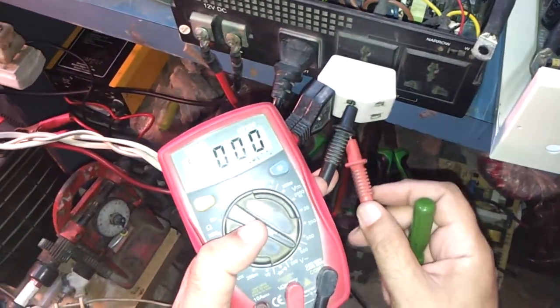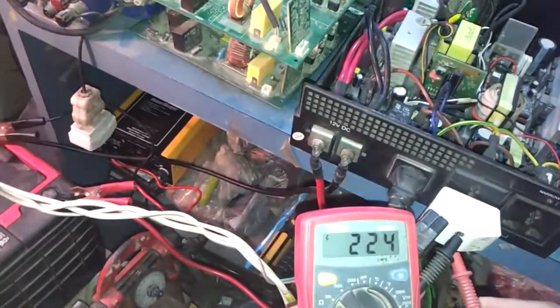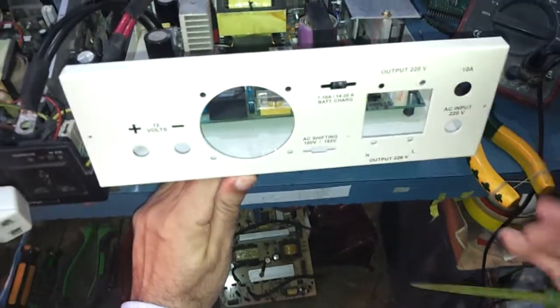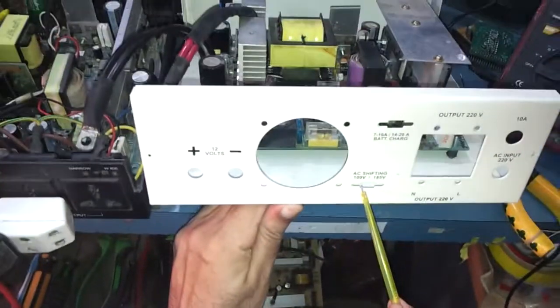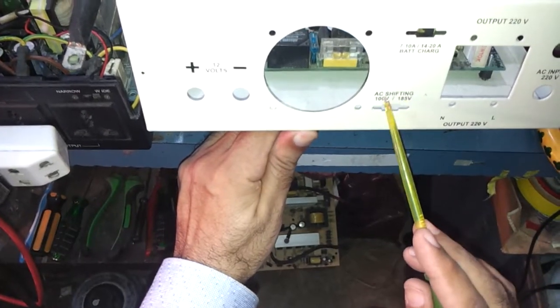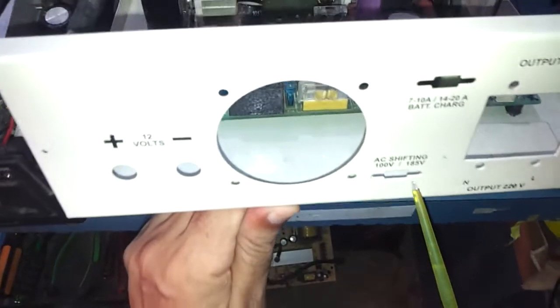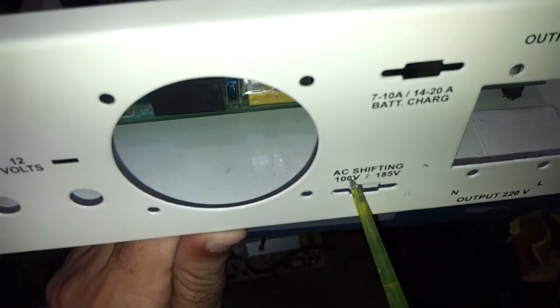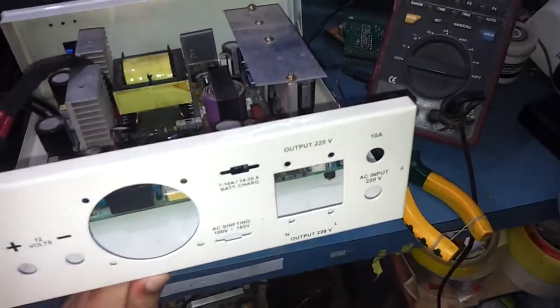AC to battery changeover voltage can be set by Zener diodes for 2 values by a selector switch from under 90 volt AC to over 190 volt AC at 50 Hz or respective voltages for 60 Hz standards when required. It also incorporates a high voltage AC mains protection set at 255 volt AC, or it can be adjusted to a different value as desired by Zener diodes.